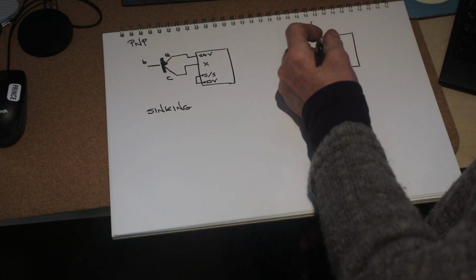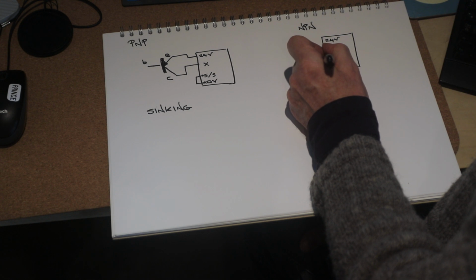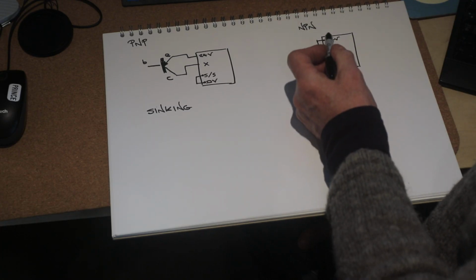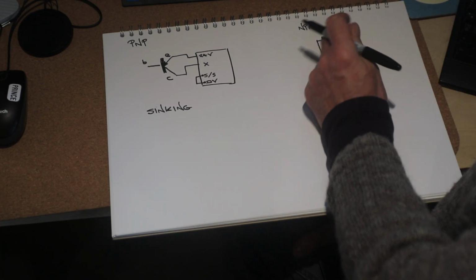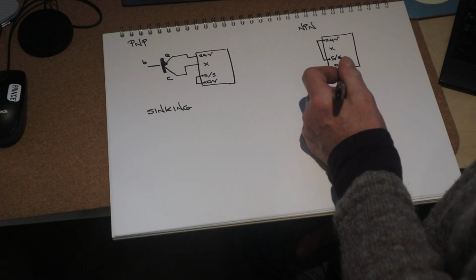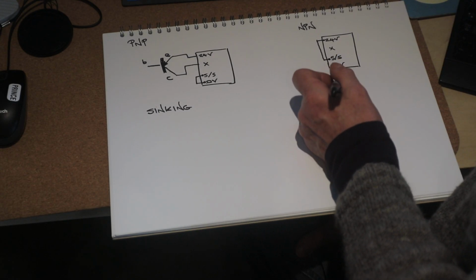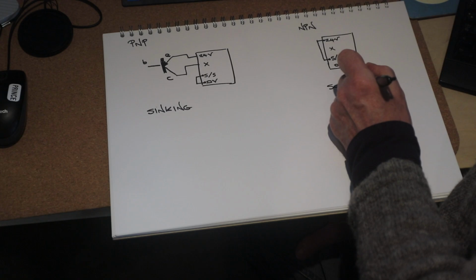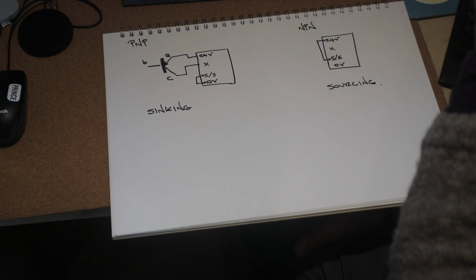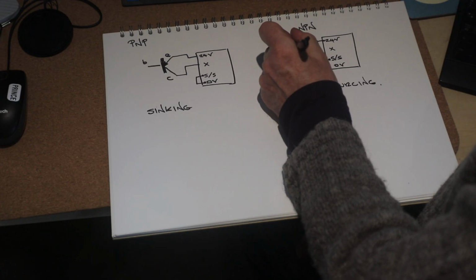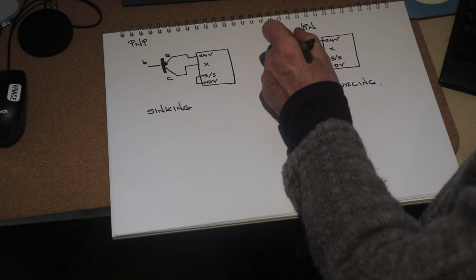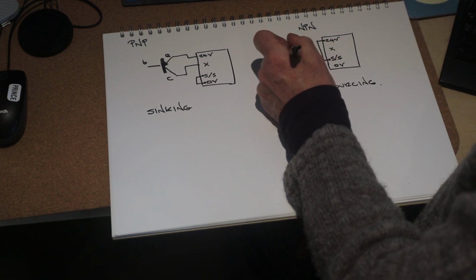But this time, I'm going to connect sinking and sourcing to 24 volts. Can you see that this time we are going to pull the power from the input rather than use it as a hole? So this one's sourcing. Okay, I've got a transistor again, but this time it's an NPN transistor, so the symbol is subtly different. It might have helped if I'd drawn the other one slightly better, but anyway, look, the arrow goes that way.